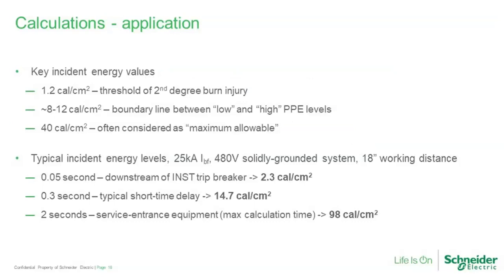Well, just a couple of things on application of the calculations. Again, I think some of you are probably familiar with these levels, but if you haven't seen this, some key incident energy values. 1.2 calories per centimeter squared is what they tell us is the threshold for second-degree burn injury. All these things are measured in percentage. You have a certain percentage chance of receiving a second-degree burn on exposed skin if you're exposed to at least 1.2 calories worth of energy. NFPA 70E, the NFPA electrical safety standard, says that you're supposed to wear arc-rated clothing if you're potentially exposed to energy levels greater than 1.2.